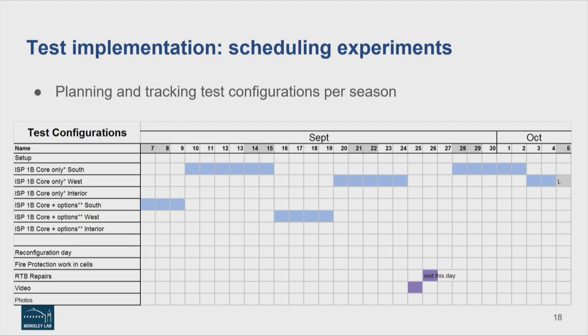So yeah, we're nimble on our feet. We come up with a schedule where we block off days to test each configuration or permutation - testing south facade windows, west facade, and an interior test where we block off the window wall with polyiso foam to mimic an interior zone in a building, comparing energy performance.